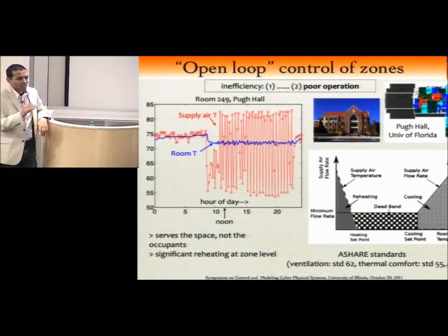So it's maintaining temperature and airflow and ventilation levels throughout the day, which is bad. The other thing is the red curve is the supply air temperature. Supply air comes in at around 55 degrees Fahrenheit, but most of the time it's actually higher. So what it's doing is the controller is reheating the air to maintain temperature. Even at 2am, midnight, nobody's there, it's reheating the air because otherwise you won't be able to maintain 72 degrees Fahrenheit, right?